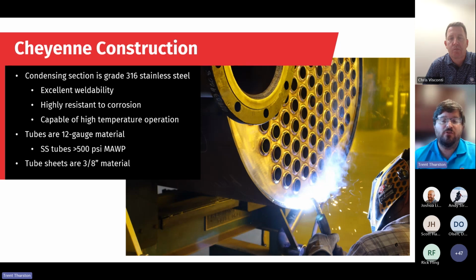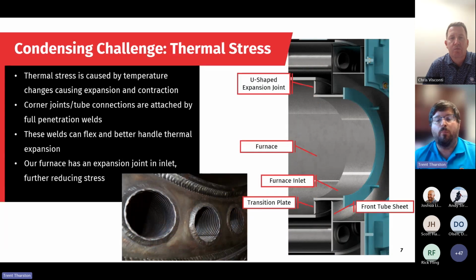So for these thermal stresses, what we do is we have full penetration welds throughout the boiler. So our tube to tube sheet joint, the tube sheet to shell, the tube sheet to furnace, all of these are done with full penetration welds. These are the best type of welds for dealing with thermal stresses. These allow us to flex, and so then it will absorb some of this thermal expansion as opposed to adding that as stress to the metal.